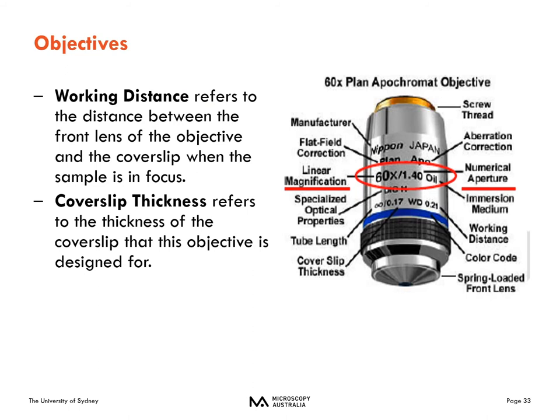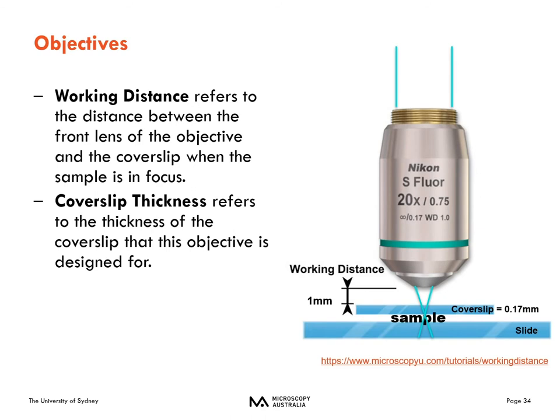The working distance refers to the distance between the front lens of the objective and the cover slip when the sample is in focus. Cover slip thickness refers to the thickness the objective is designed for — the standard is 0.17 mm, which is a number 1.5 cover slip. So the distance between the objective and your sample is the working distance plus that cover slip thickness of 0.17 mm.